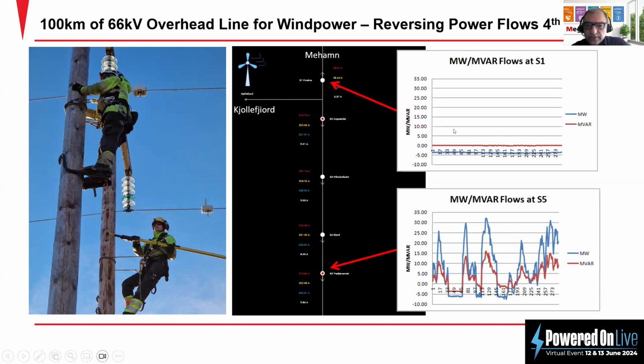And as you can see, for sensor 1, when the wind farm is, the minus normally means importing from the network, and plus means exporting to the network. And here it is always importing from the network, while at the same time, S5 is recording the main substation, and during the one day they have 4 peaks, which means 4 times they change the importing and exporting from the network, which enables them to make decisions and manage the load management and the power flow in the network.